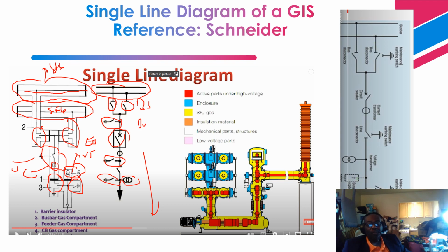Okay, so now let's talk about this diagram, right? Okay, so this is an apparatus bushing, right? And I went through that with you on the previous slide. So I explained how this is in the form of a zigzag. It's to increase the creepage distance and also prevent leakage current from reaching the ground plane. Remember, this is a flange here, right? And that is the ground plane, and the goal is to prevent leakage current from reaching there faster, and basically to prevent a flashover. Okay, so you can have an overhead line come here and basically get connected over here, right?